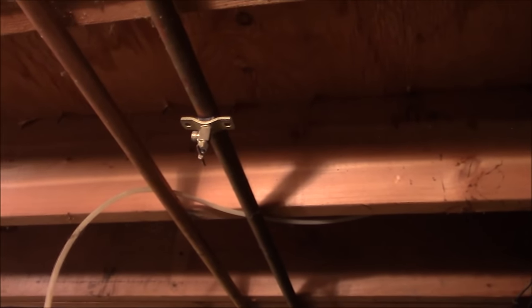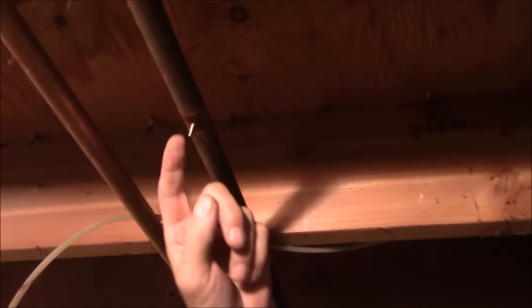Here's the old valve and you're about to see the piercing. I pulled off the valve. The center stem of the valve stayed in the copper. You can see it has a sharp point — it was designed to cut into the copper as the valve was clamped onto the copper pipe.